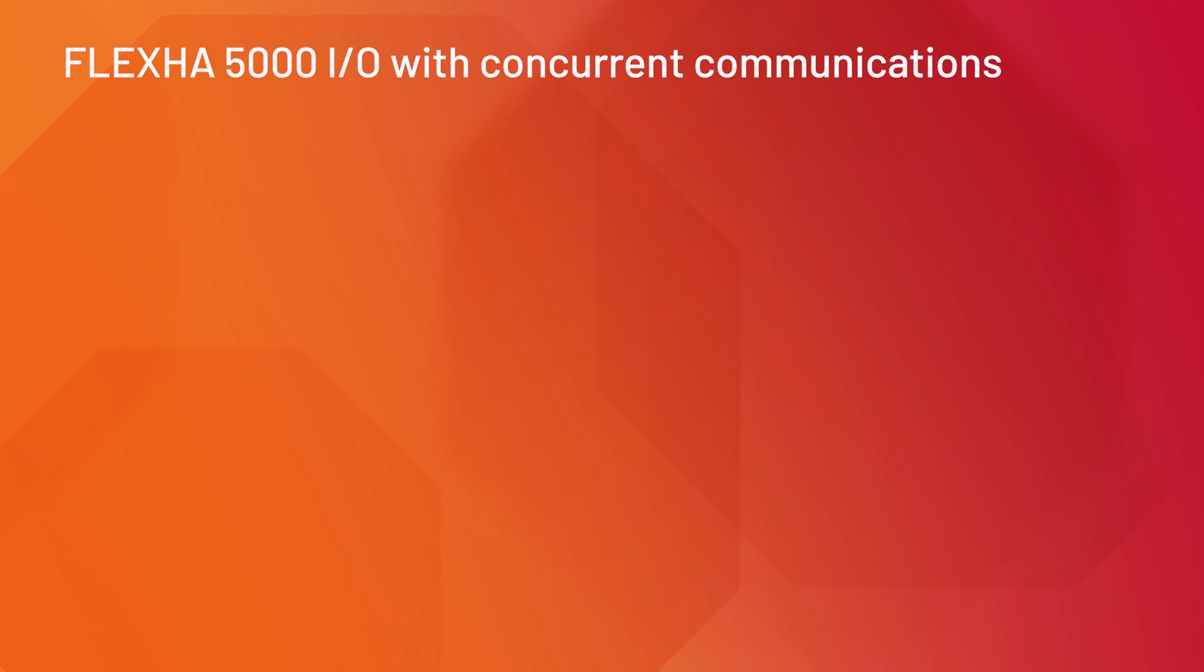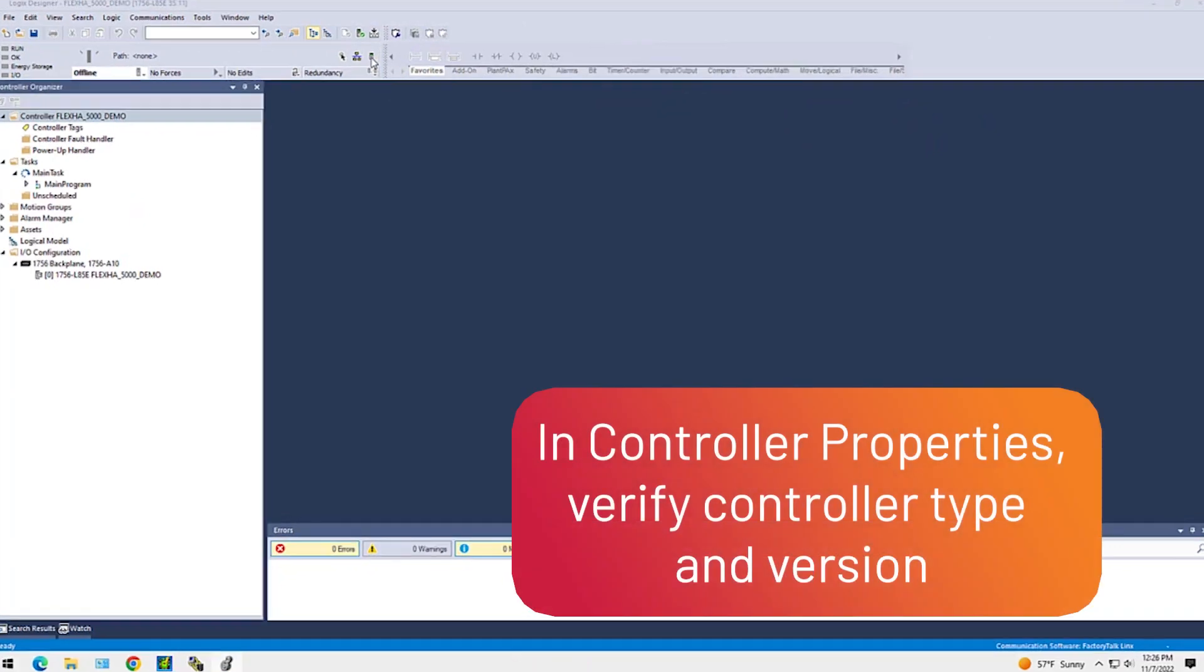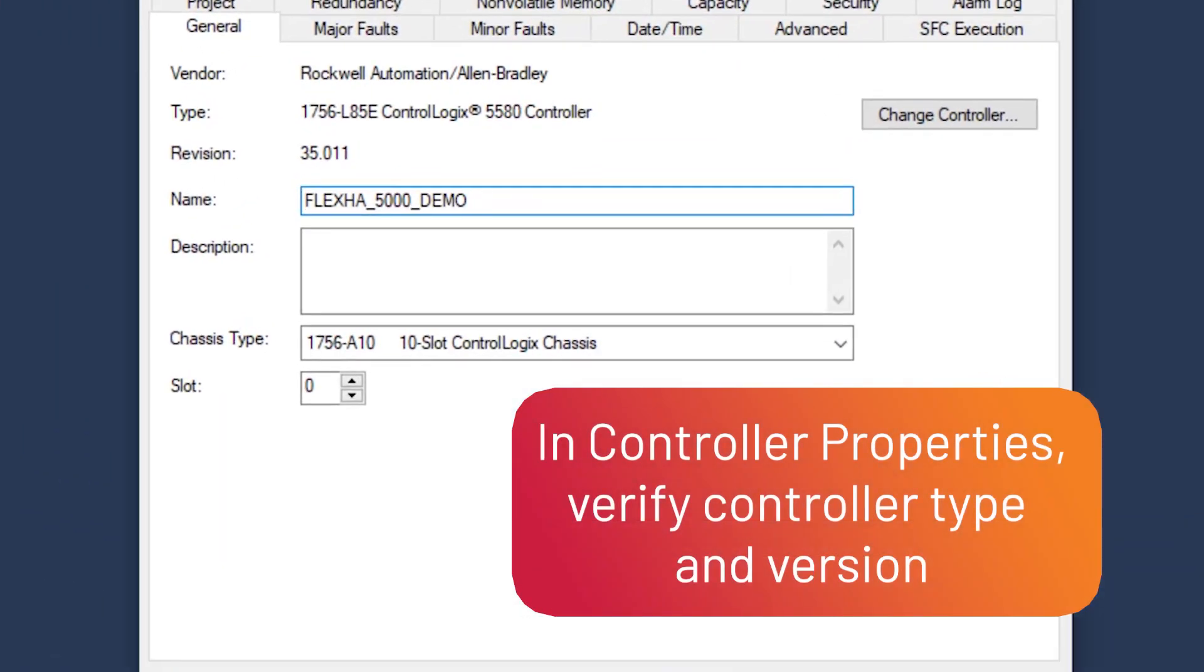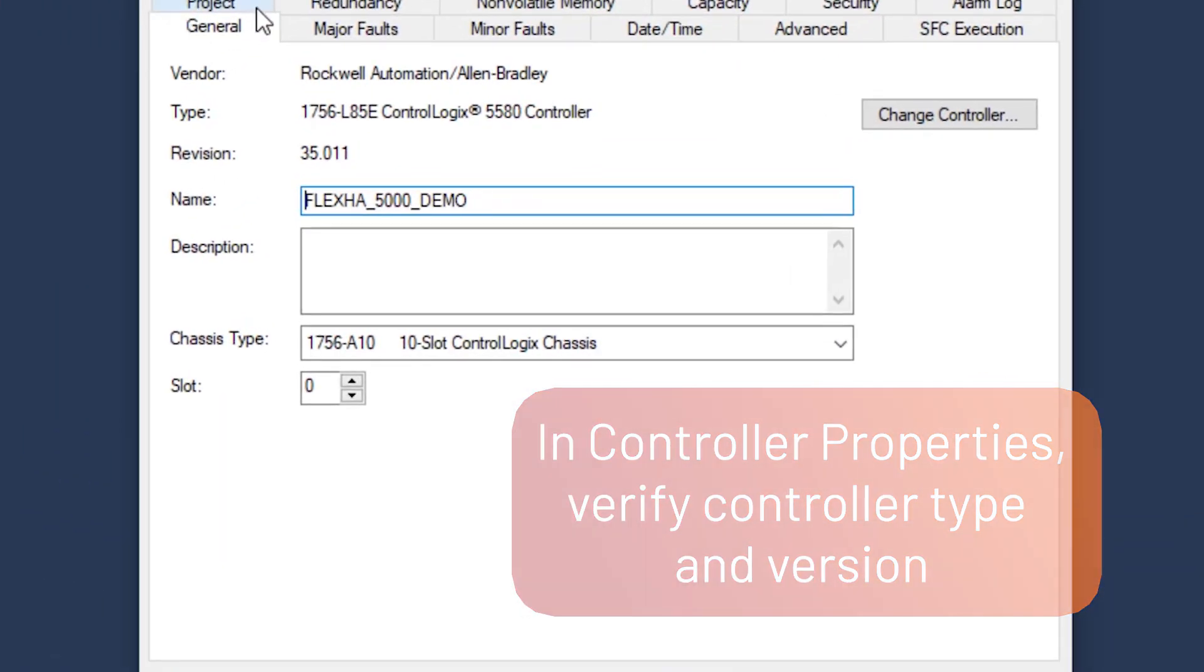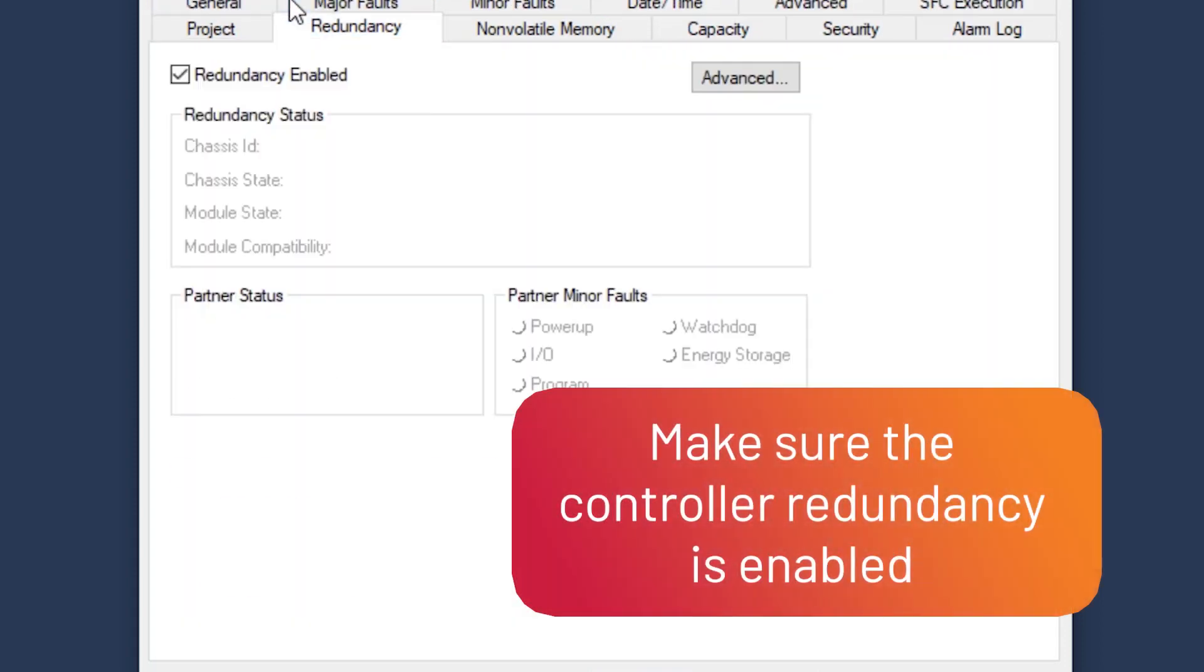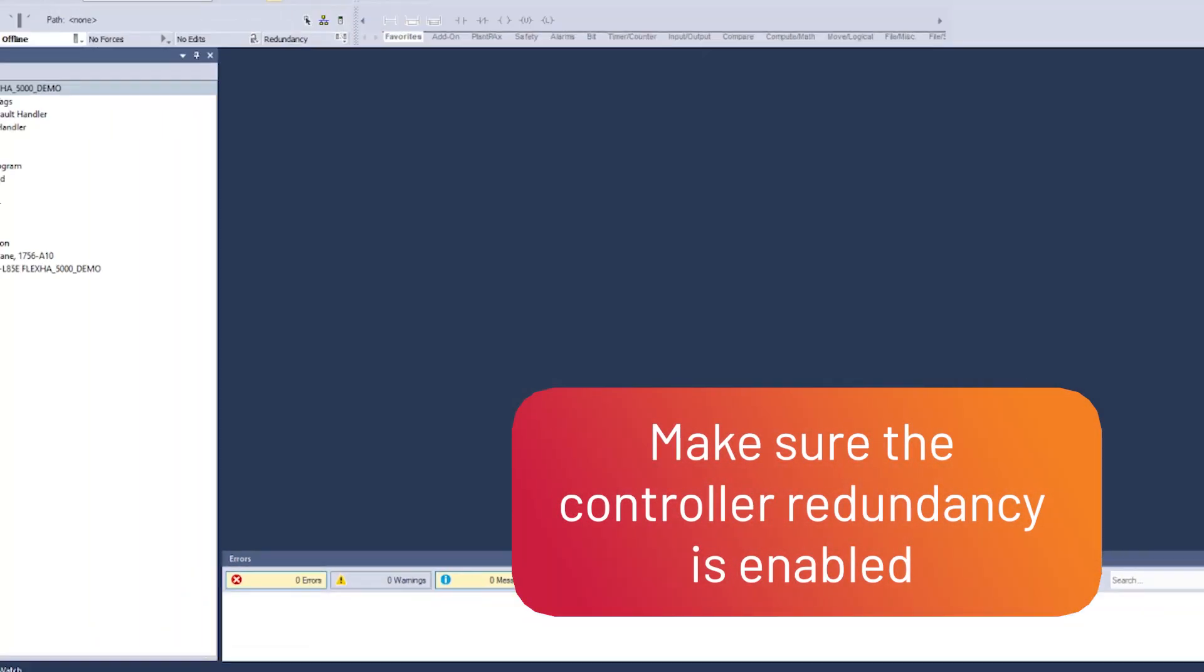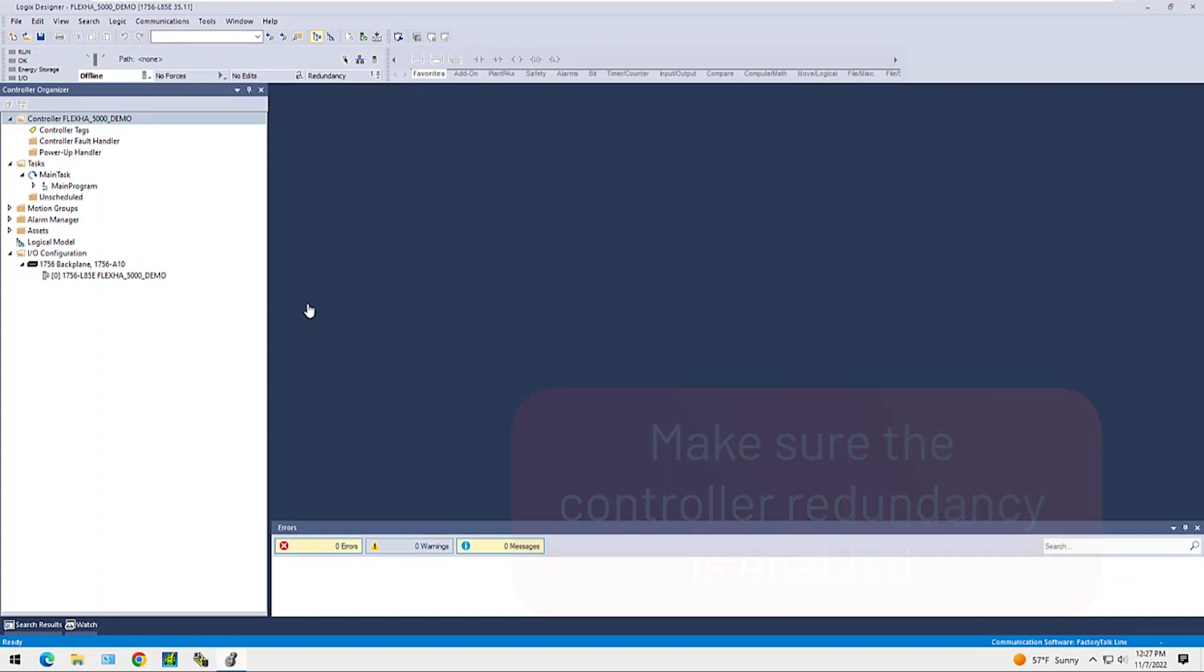Let's see how it all works with the Concurrent Communications software. In the Controller Properties, verify the controller type and version. Make sure the controller redundancy is enabled within the software when ControlLogix redundancy is implemented.